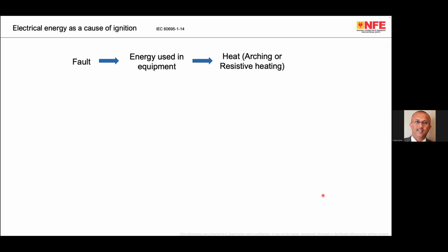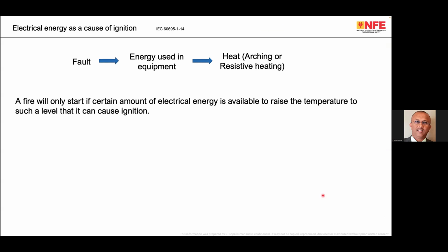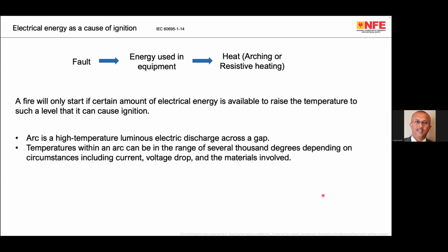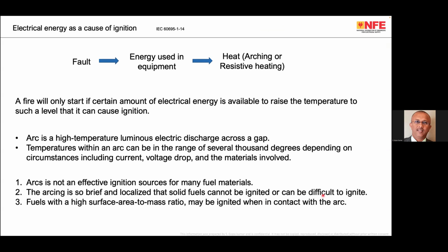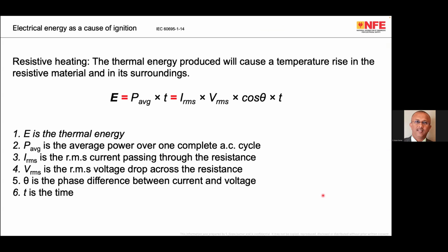With respect to fault and fire, a fault is proportionate to the energy used in the equipment, which is proportionate to the heat, arcing or resistive heat, which is produced because of a fault. Let me skip a little bit of this too much theory part. It is the energy which creates the thermal effect, not fire, sorry, thermal effect. The thermal energy produced from the appliance is the reason. The thermal energy is calculated as the average power multiplied by the time, so I into V into T. You can find this information in the standard 60695 part 1-14. So basically, the standard analyzes the reason for fire.